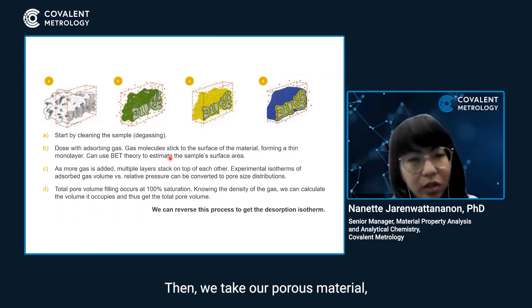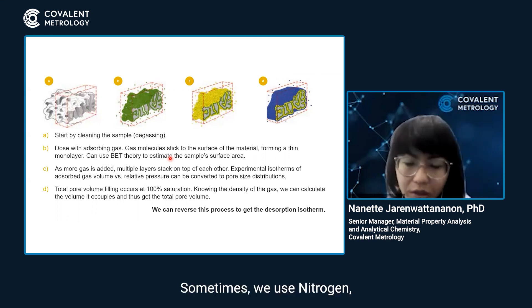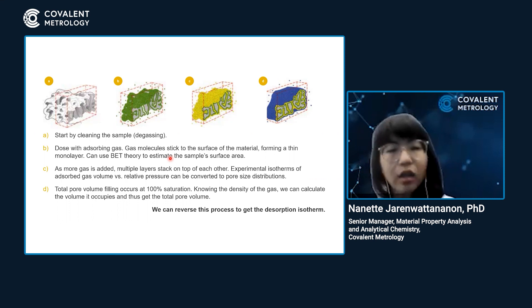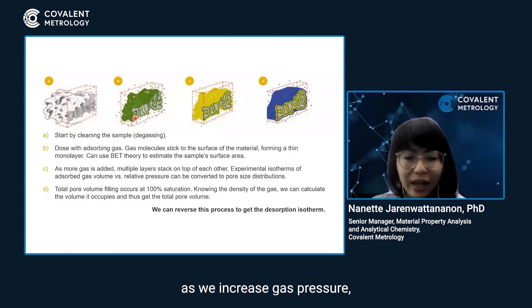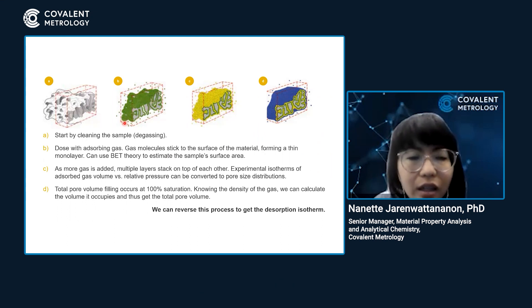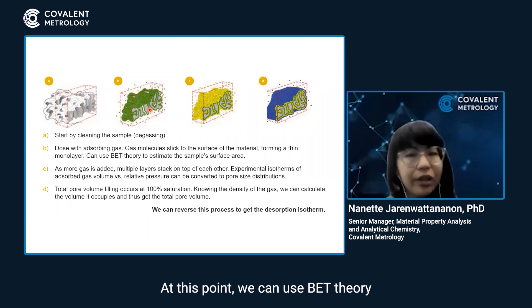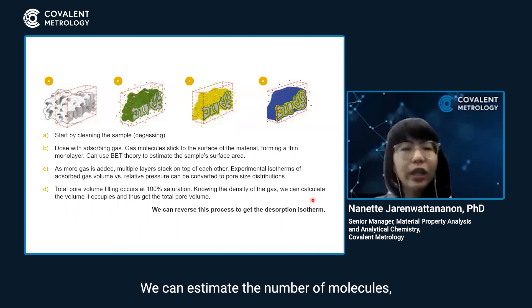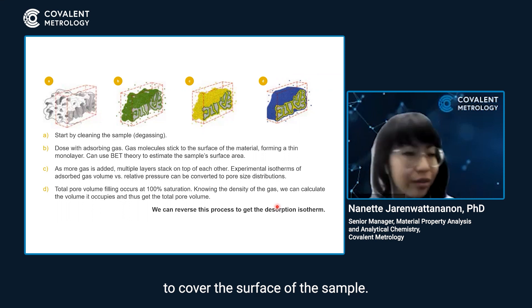Then we take our porous material and dose it with an adsorbing gas — sometimes nitrogen, sometimes argon. The choice of gas depends on your particular application. As we increase gas pressure, gas molecules start to slowly stick to the surface of the material, forming a thin monolayer first. At this point, we can use BET theory to estimate the surface area of a sample — essentially estimating the number of molecules required to cover the surface.